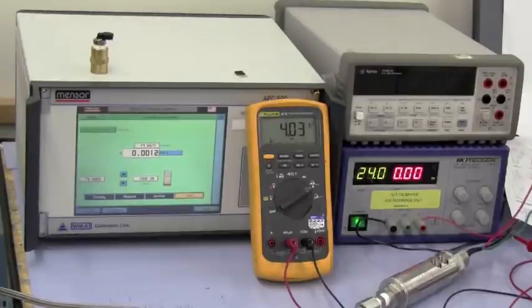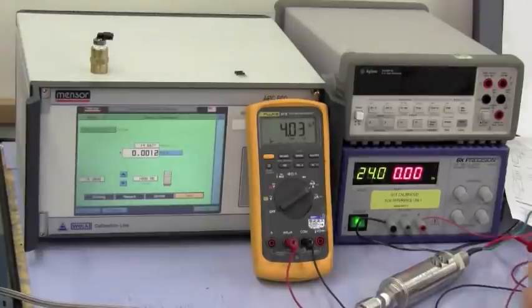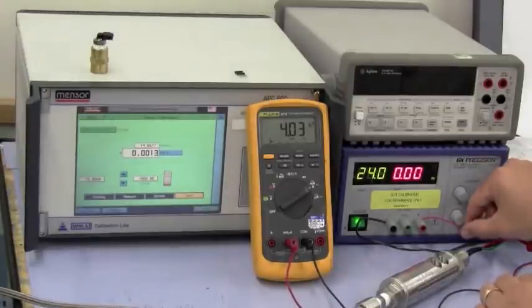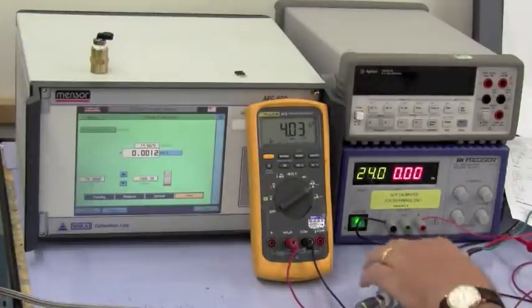I've taken the red wire, the positive wire from the transmitter, and attached it to the negative terminal of the multimeter. And then I've connected the positive from the multimeter to the positive of the power supply. So now we're ready to span the transmitter.